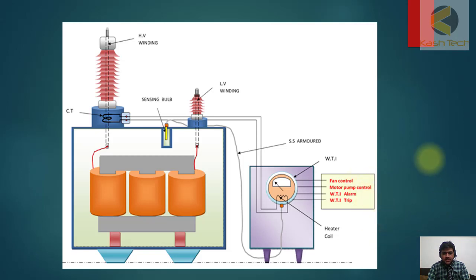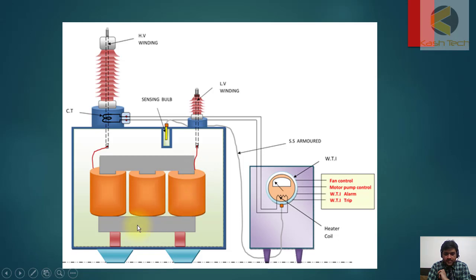Here is an example showing the HV bushing connected to the HV winding, and the LV bushing. You can see the sensing bulb, which is connected to fan control, motor pump control, temperature alarm, and tripping alarm. This entire setup is for the winding temperature indicator.